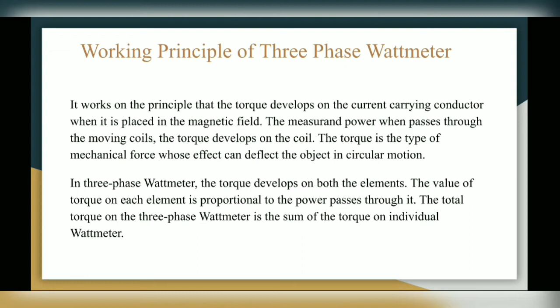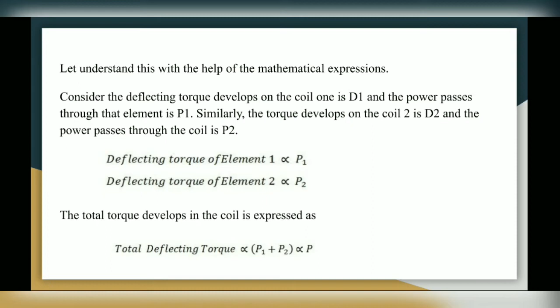Let's understand this with the help of a mathematical expression. Consider the deflecting torque developed on coil 1 is D1 and the power passing through the element is P1. Similarly, the torque developed on coil 2 is D2 and the power passing through the coil is P2. So the deflecting torque of element 1 is directly proportional to P1 and the deflecting torque of element 2 is directly proportional to P2. The total torque developed in the coil is expressed as: total deflecting torque is proportional to P1 plus P2, which is directly proportional to P.